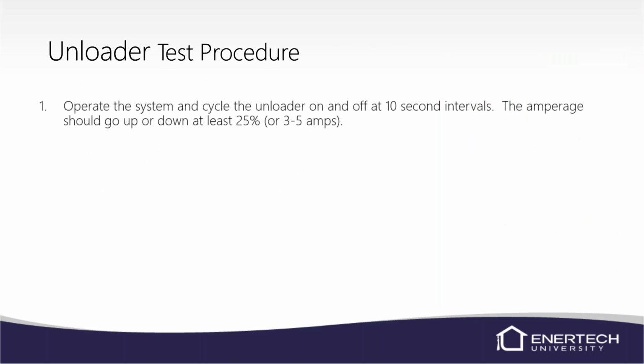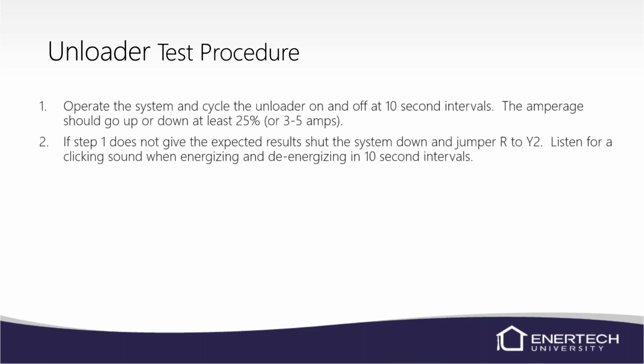The unloader, which is basically that low voltage harness on the compressor, if you want to test it, you can operate the system and cycle the unloader on and off. And again, the amperage should go up or down. You can also jumper, just remove the call for the compressor, so you can hear, you don't have a fan running or the compressor causing noise. Just jumper R to Y2 and listen for a clicking sound at the compressor.